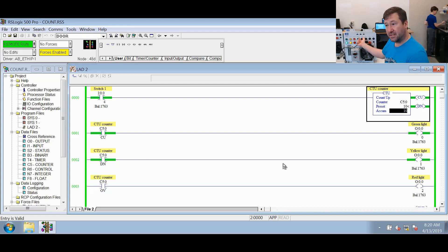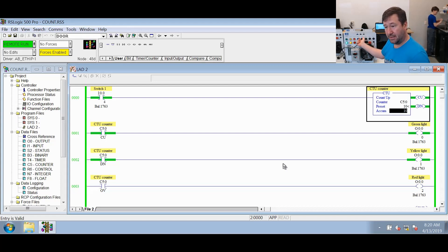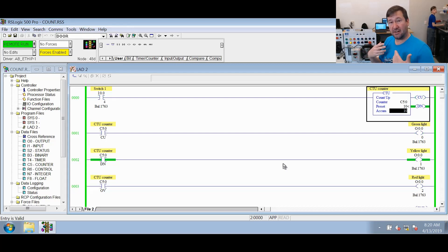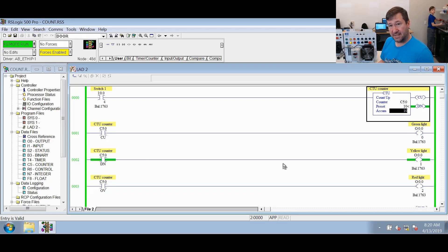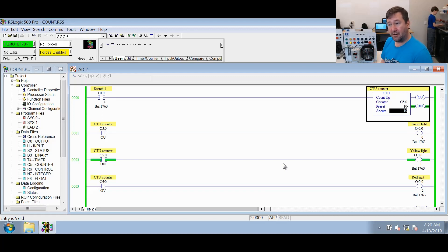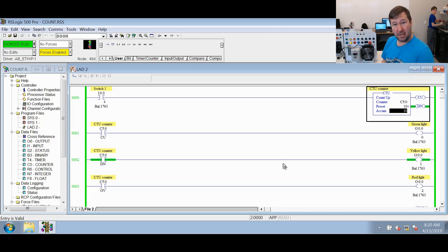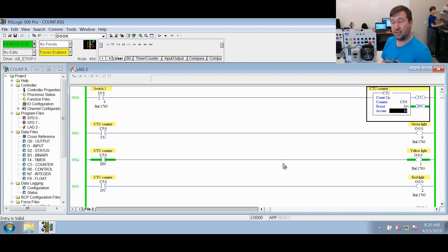Let's go ahead and switch this switch off. That way we make sure we understand how this done bit works. So see our CU bit went back off, but our done bit stayed on. So the done bit of a count up counter means that the accumulated value is greater than or equal to the preset.